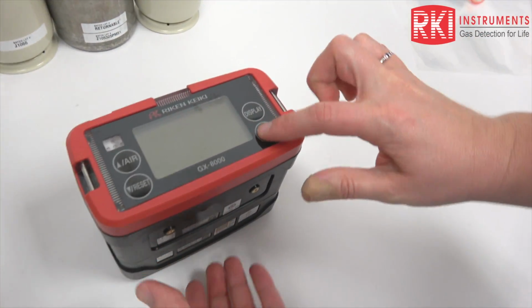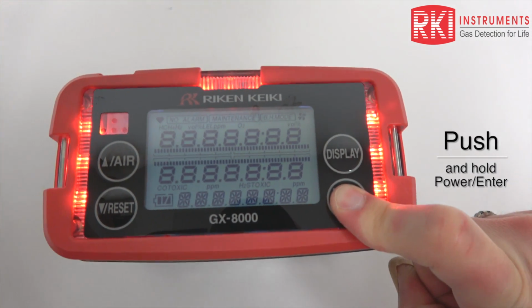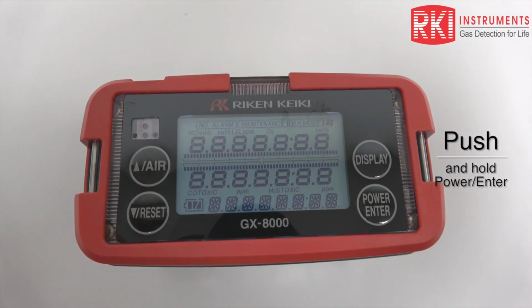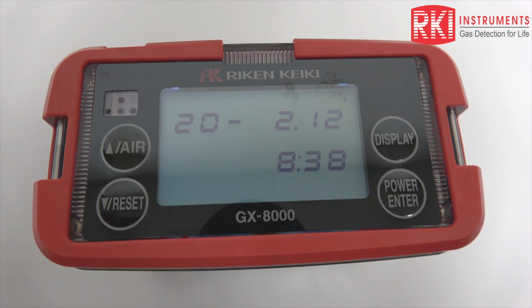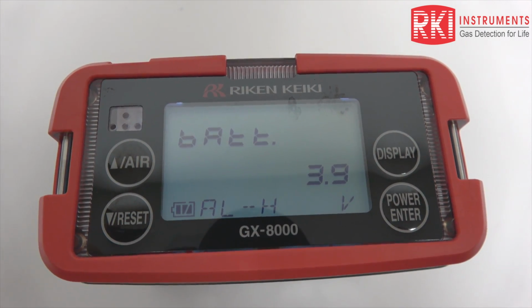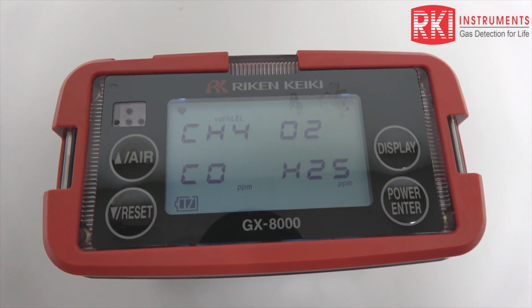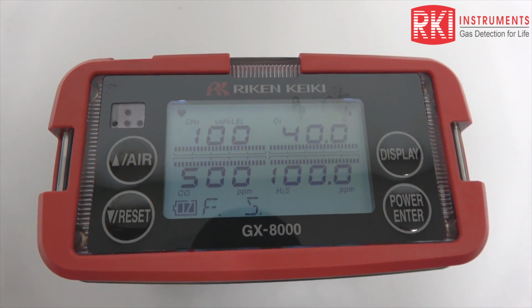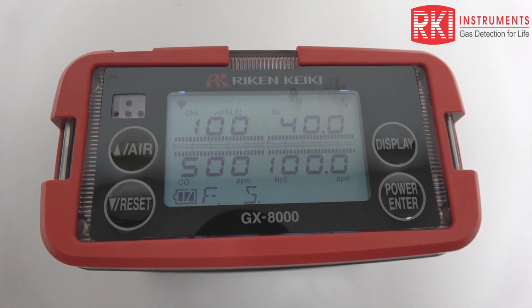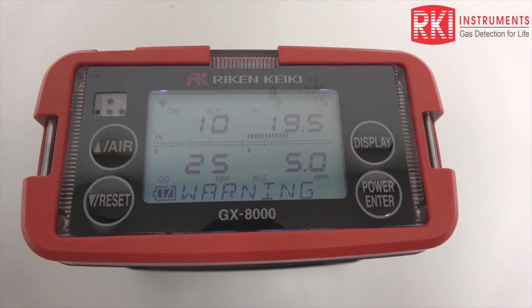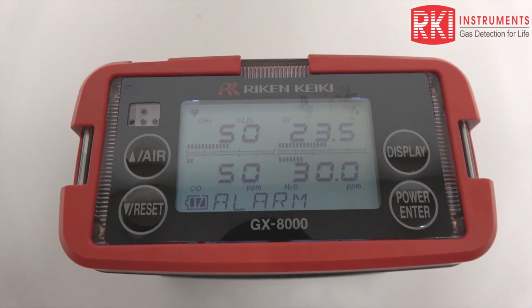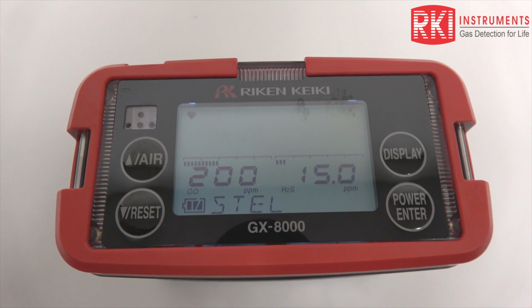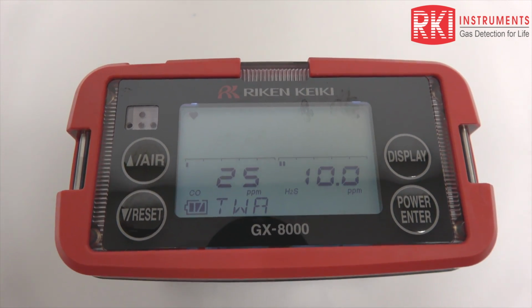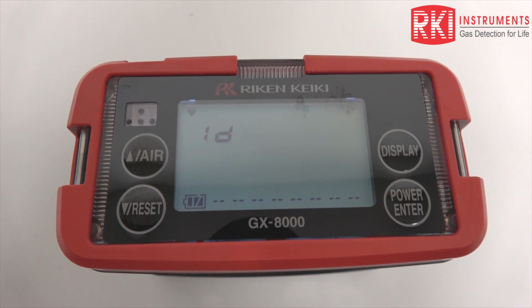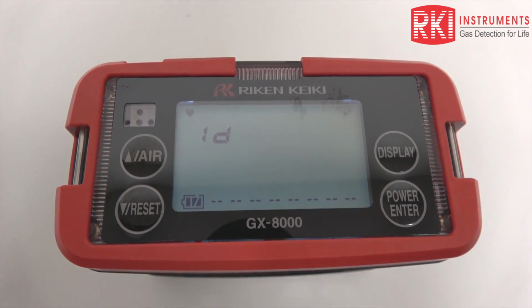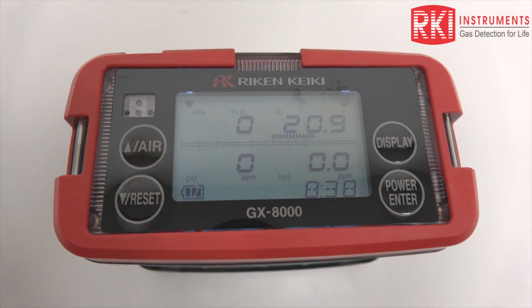We need to turn our instrument on using power enter. It's going to go through its warm-up sequence. There's the date and the time, and the battery voltage. Those are the gases that are installed in this particular unit and their full scales. The warning and the alarm set points show. And then the STEL and TWA for the CO and H2S sensors. This is the ID screen. I don't have an ID programmed into this instrument. And then this is the normal operating screen.